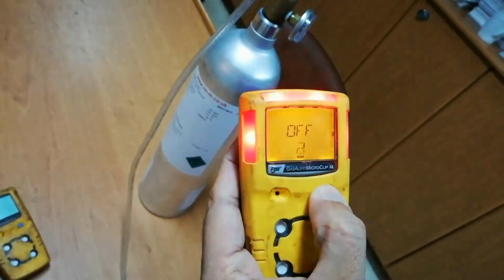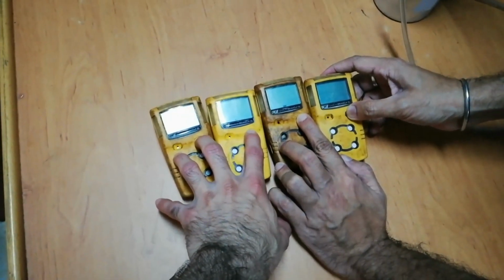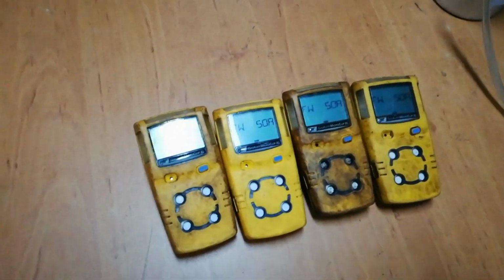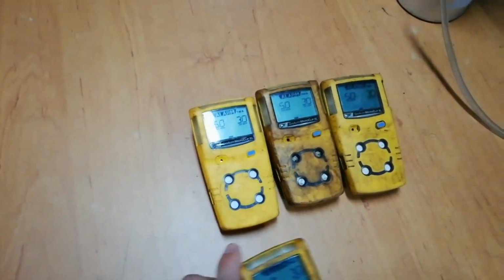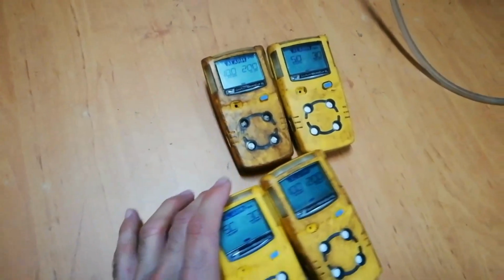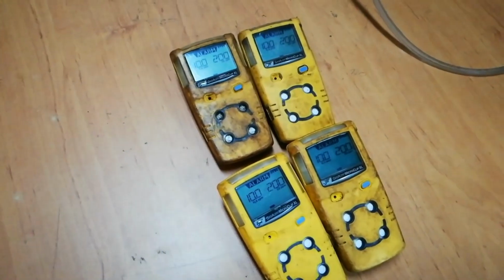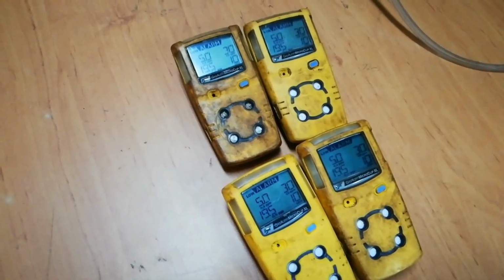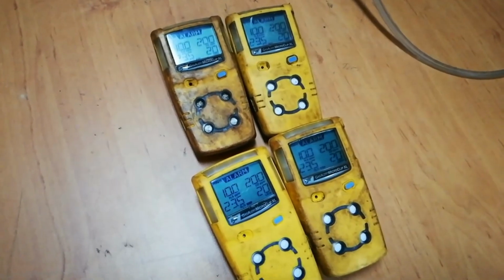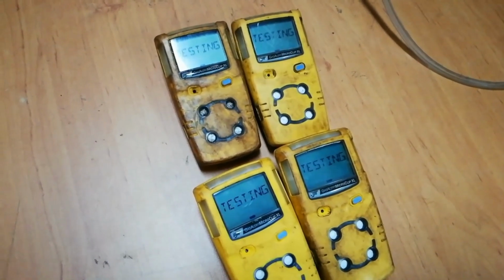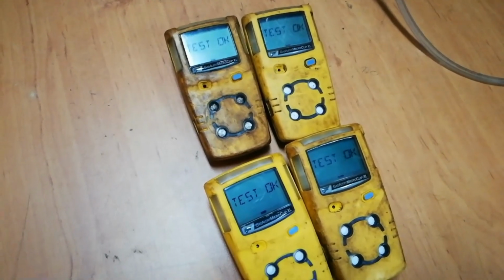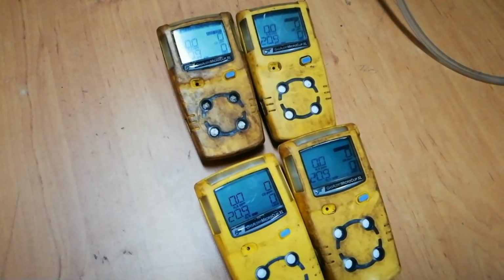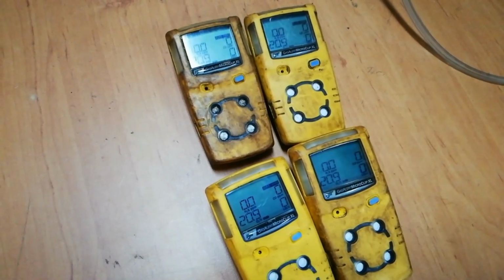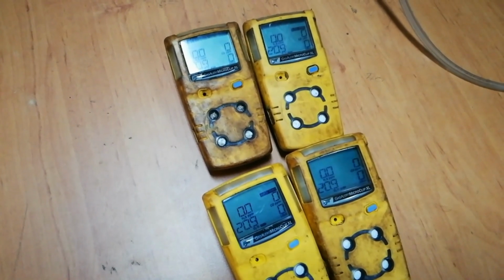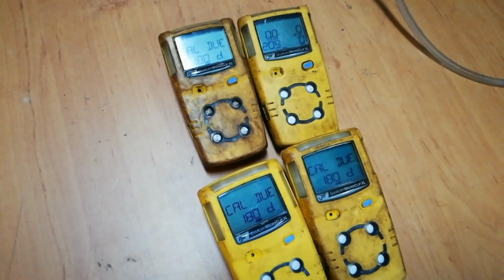So it means the calibration is completed, and I have done the same for my other Microclip XT multi-gas detectors. All four sets of these multi-gas detectors I have calibrated today, and here you can see the due days for the next calibration. It will start the self test, and we have to wait for the self test first. Normally every 2 years we have to do the full calibration, and every month we have to do the onboard calibration. Now the self test is completed, and here you can see the remaining days for the next calibration as 180 days.